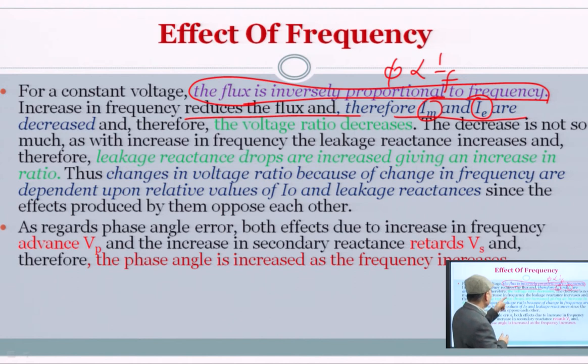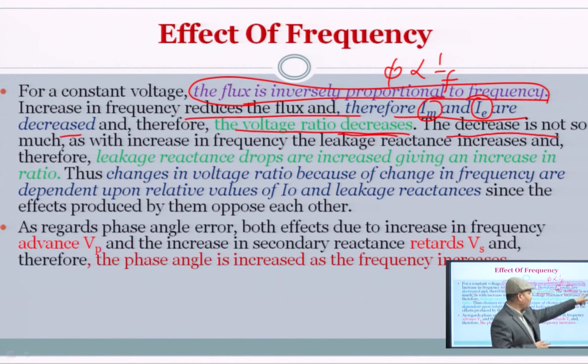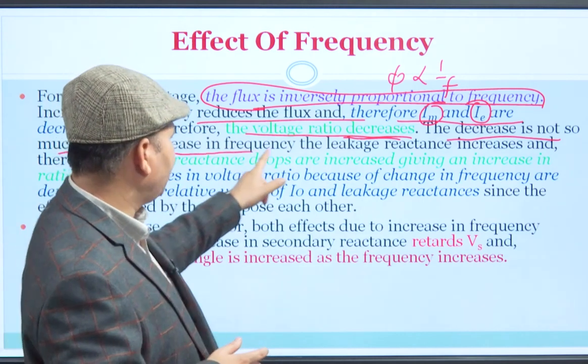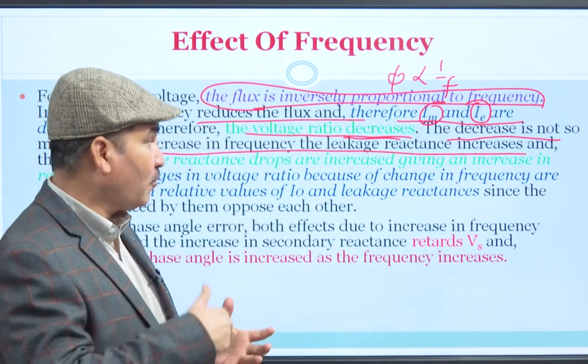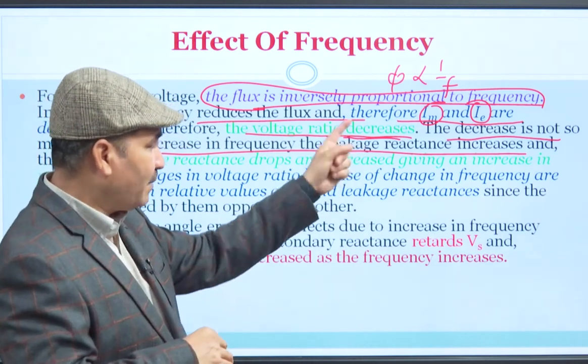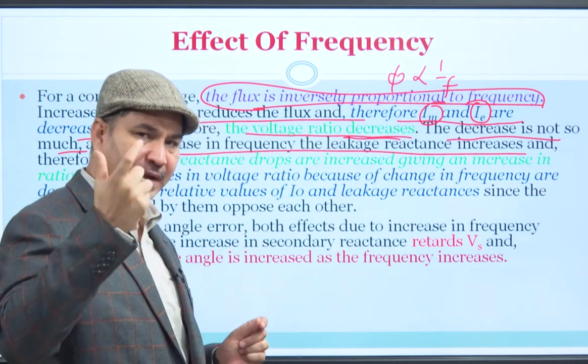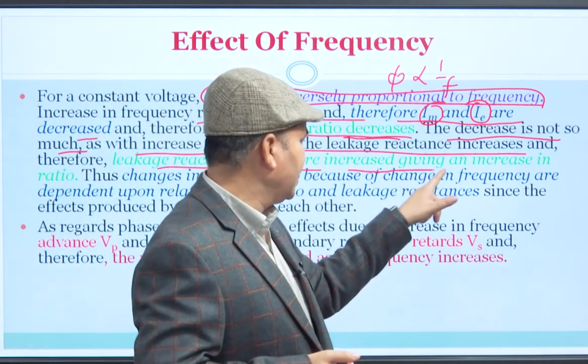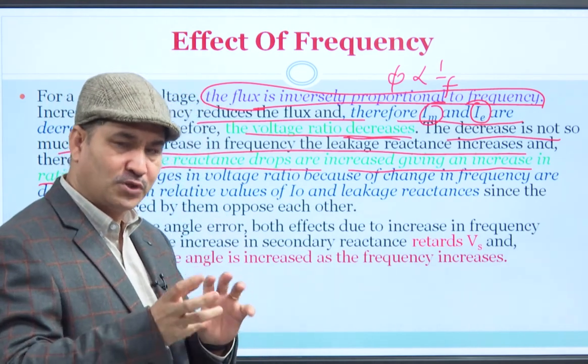However, the voltage ratio decreases when IM and IE decrease, which is desirable — errors are reducing. But at the same time, with increase in frequency, the leakage reactance also increases because the omega factor increases, so leakage reactance drops increase, leading to an increase in ratio error. So on one side, the ratio error is decreasing (due to reduced IM, IE), and on the other side, leakage reactance is increasing it — they neutralize each other.